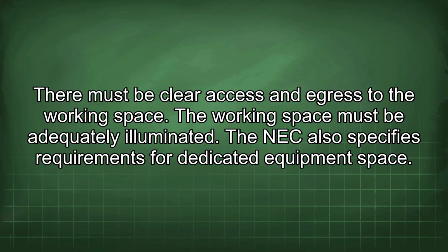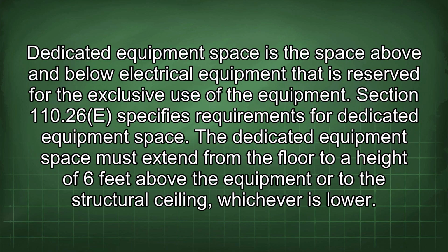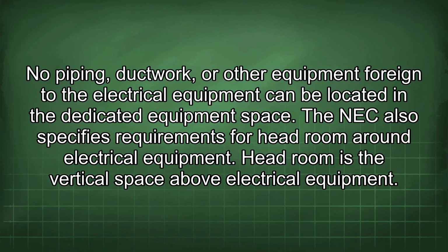The NEC also specifies requirements for dedicated equipment space. Dedicated equipment space is the space above and below electrical equipment that is reserved for the exclusive use of the equipment. Section 110.26(E) specifies requirements for dedicated equipment space. The dedicated equipment space must extend from the floor to a height of 6 feet above the equipment or to the structural ceiling, whichever is lower. No piping, ductwork, or other equipment foreign to the electrical equipment can be located in the dedicated equipment space.